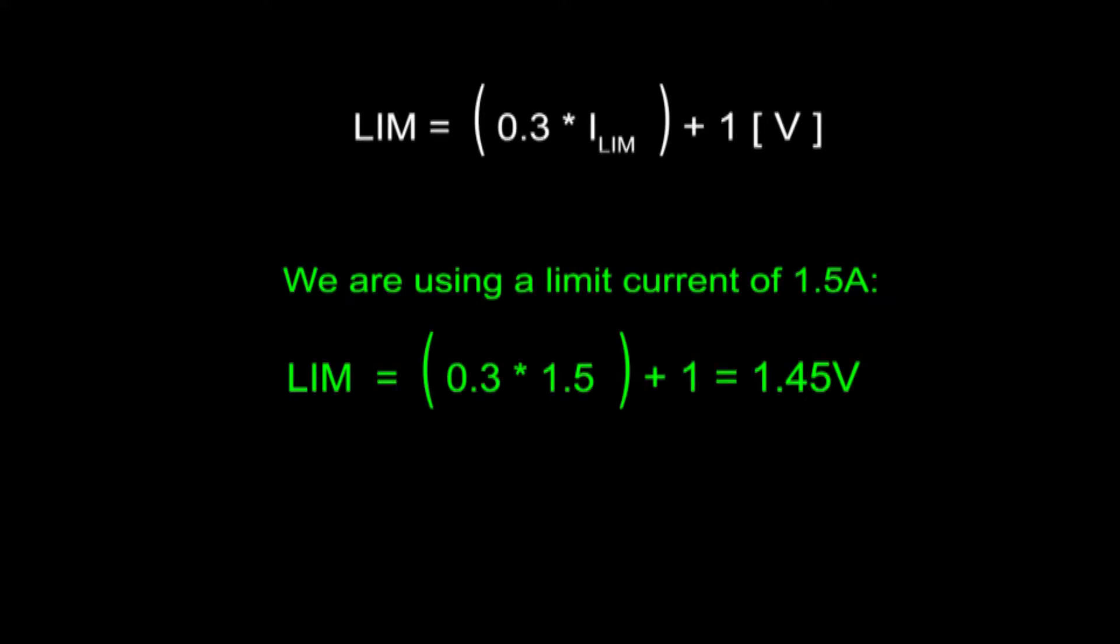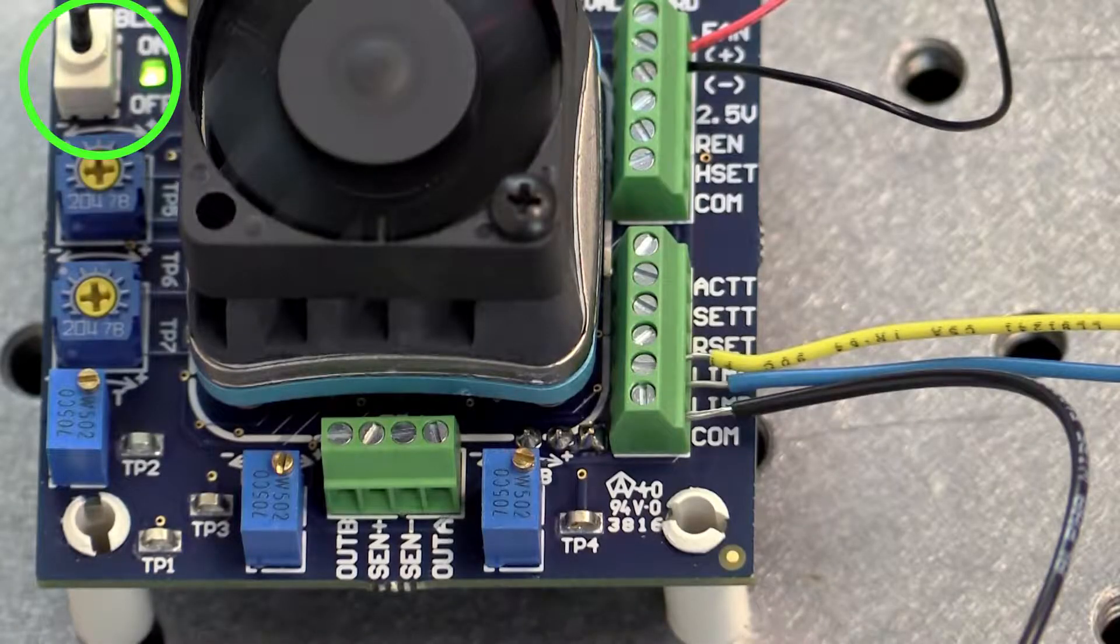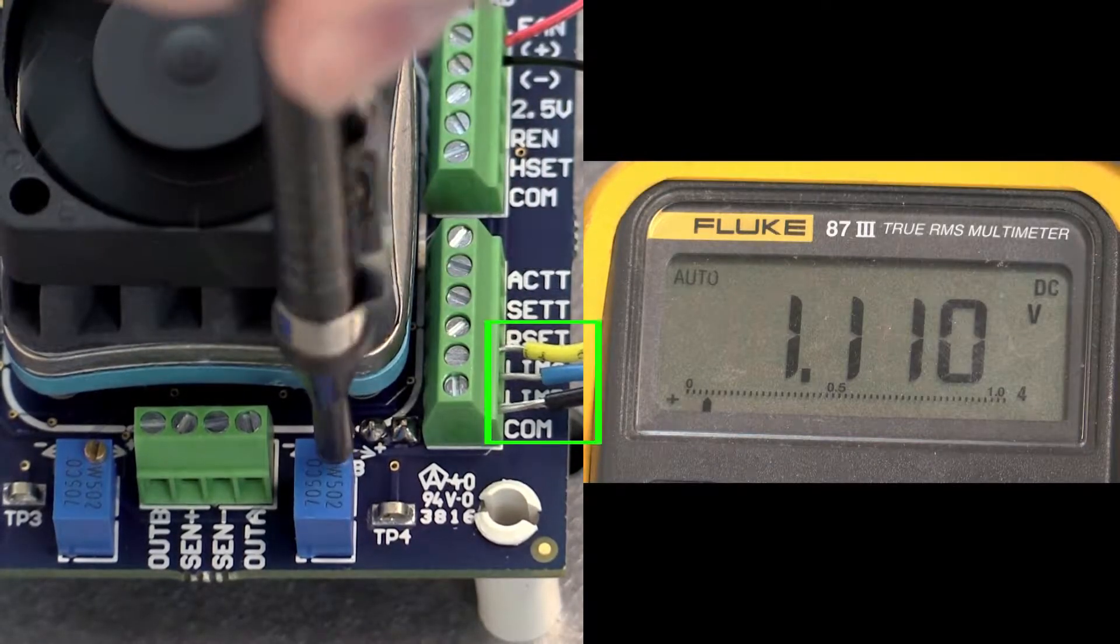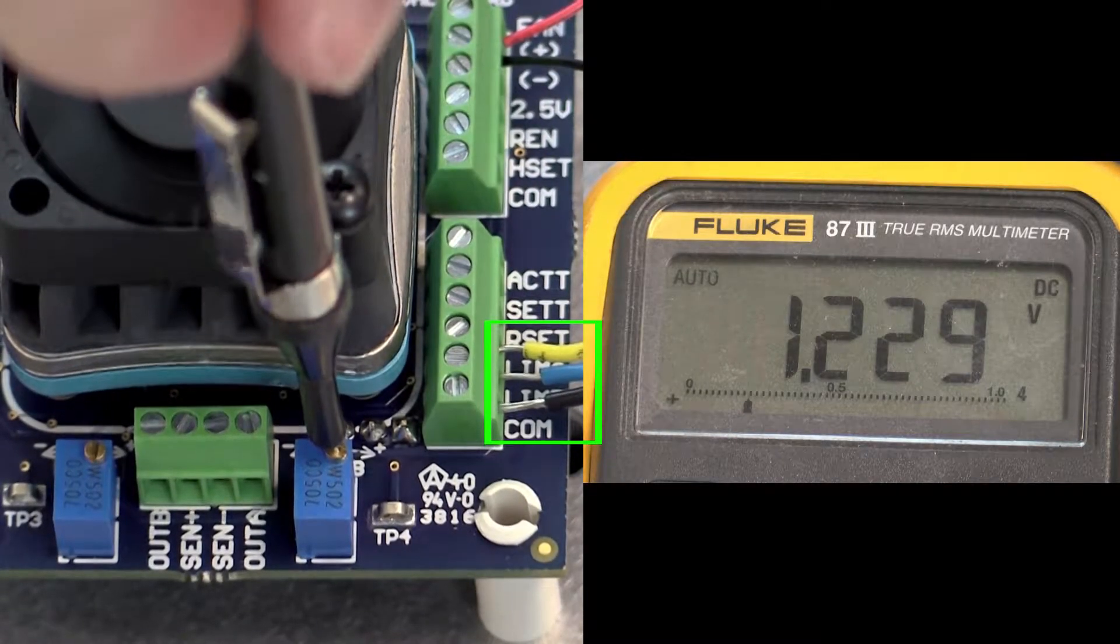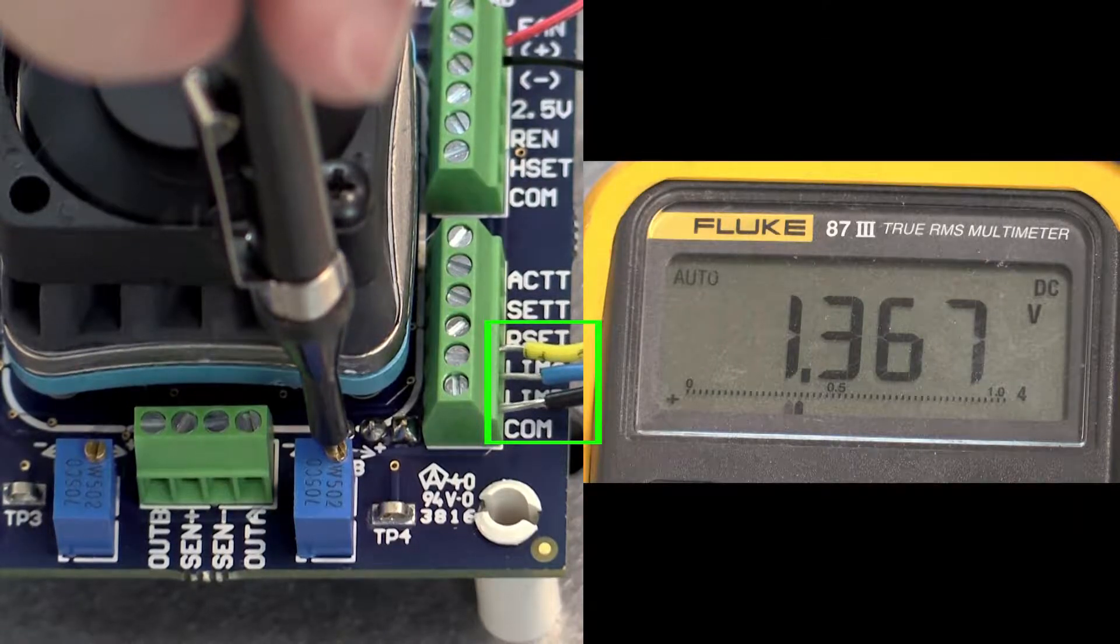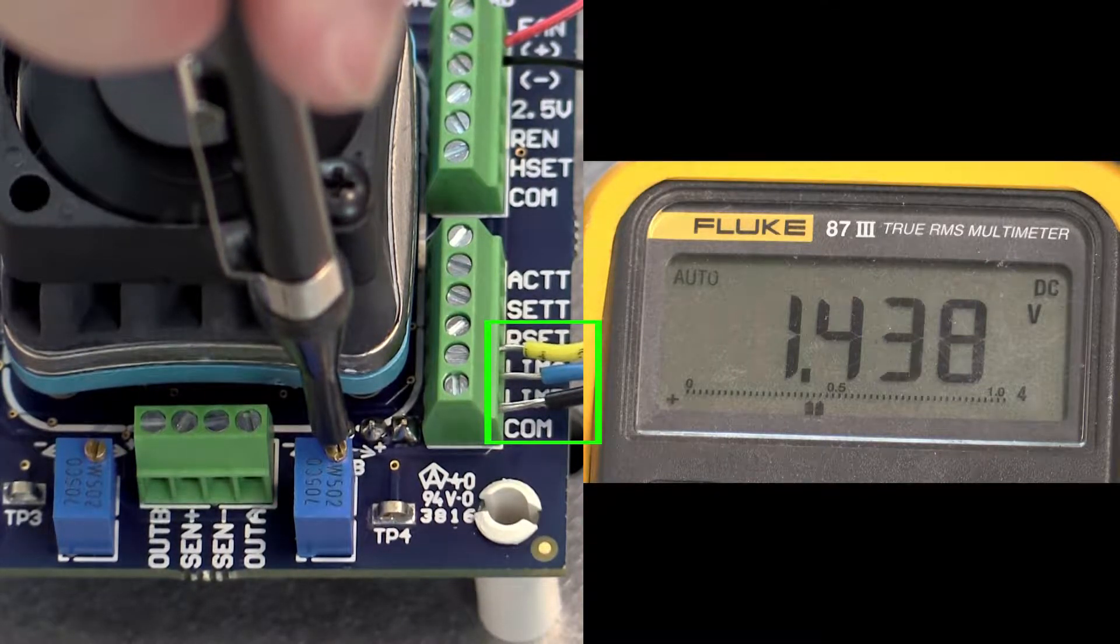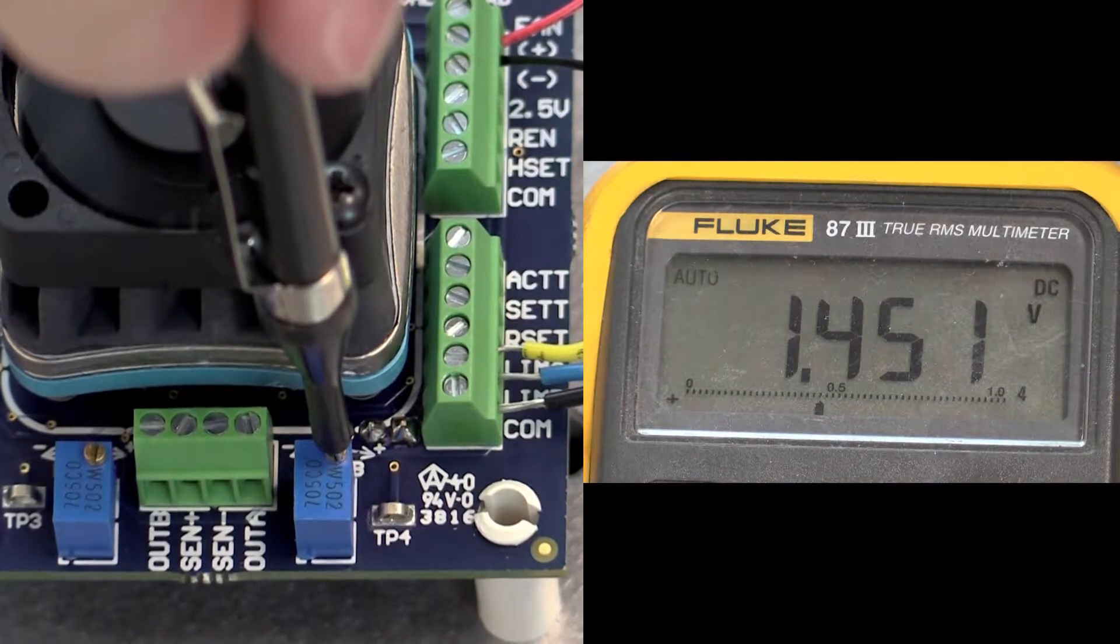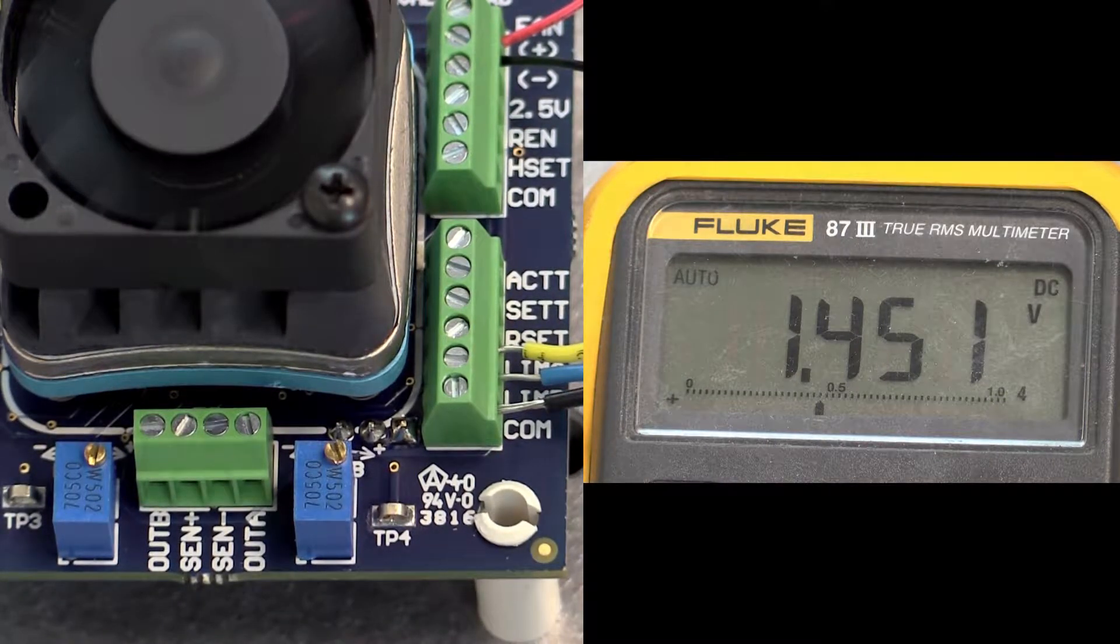Once the limit values are determined, toggle the enable to ON to apply power to VDD and VS. No load required. Rotate the LIM trim pot and monitor the respective voltage at LIM A and LIM B on TB3. Use COM as ground reference. Turn the trim pots counterclockwise to reduce the limits or clockwise to increase them.